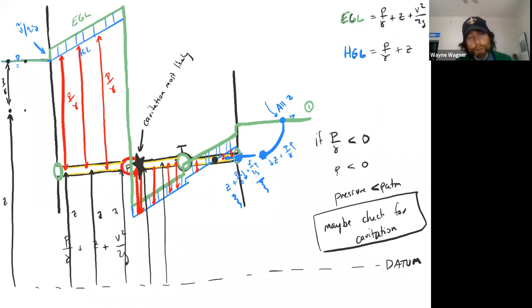Now, obviously, if you do the math and you discover that cavitation will happen right there, then you need to figure out how far back this way the pressures drop low enough that we need to worry about cavitation there. So that's just one thought. Now notice all of a sudden we hit the pump and we're really pressurized, and cavitation is no longer really a possibility.